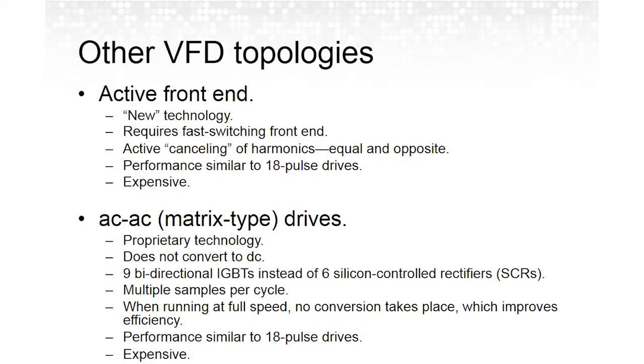And the performance that we can get from these is very similar to 18-pulse drives, but right now they're very expensive. There's not a heck of a lot of market penetration right now just due to the cost and complexity and the fact that most people in the mechanical industry consider VFDs to be commodity items, and unless there are serious problems with power quality, they aren't really considered.